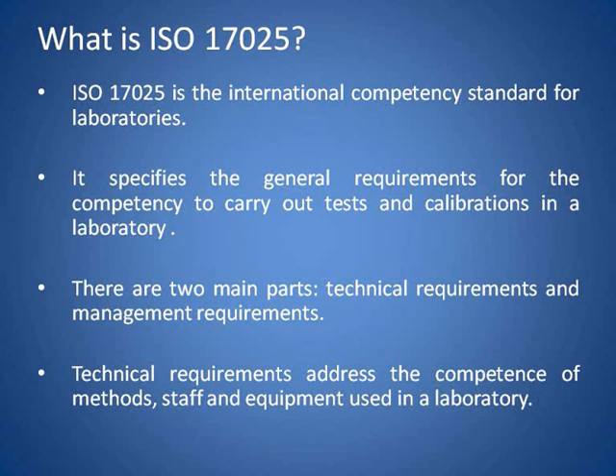The technical requirements deal with the methods, equipment, and staff used in the laboratory. Laboratories have to show that the methods they use are appropriate for their intended use. These include sampling, handling, storage, and preparation of items to be tested and calibrated. ISO 17025 requires that the methods to be used have to be either standard methods or laboratory developed methods that have undergone a validation process. The requirements also specify that the laboratory should have all the appropriate equipment to carry out all the tests and or calibrations it performs.